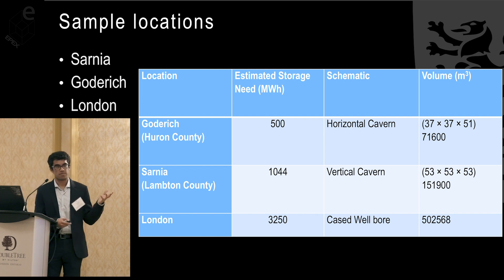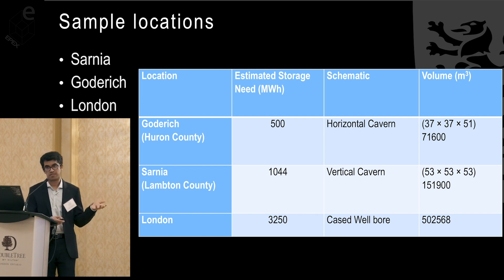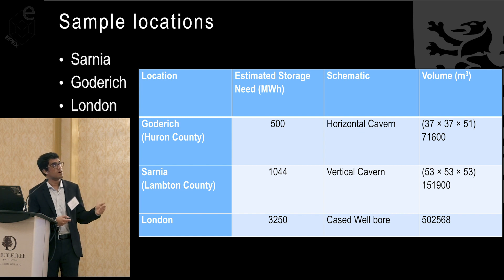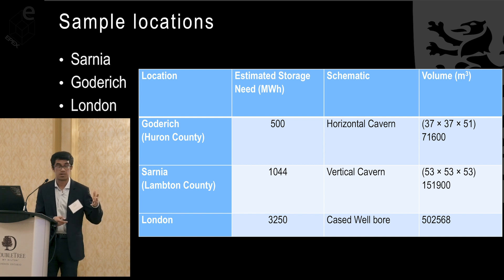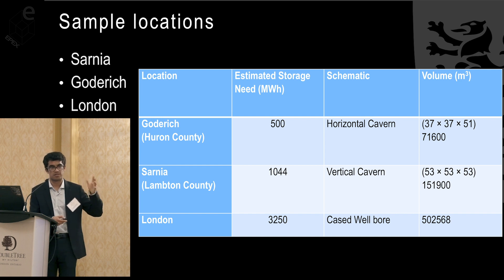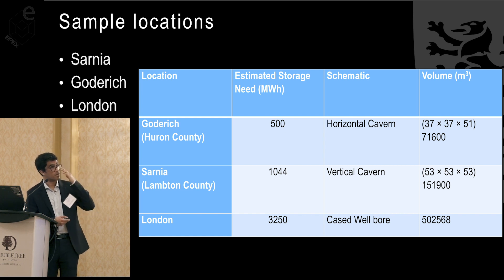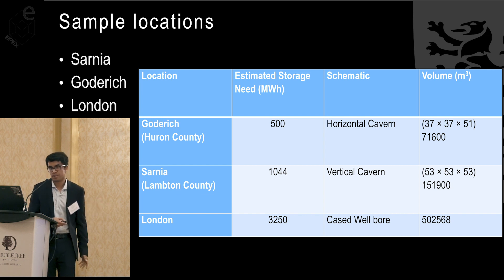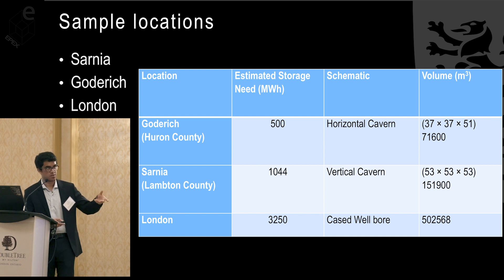To give some context, I've crunched rough numbers using the calculator to illustrate where CAES would fit. We have three locations: Sarnia, Goderich, and London, Ontario. The estimated storage is based on per capita power usage in Ontario multiplied by the local population, then taking 5% of the base load for storage. I use the same mechanical equipment across all three cases. In Goderich, with a 500 megawatt-hour need and a horizontal cavern, I've come up with dimensions of 37 by 37 by 51 meters running along the horizon, suited to the thinner salt deposit.